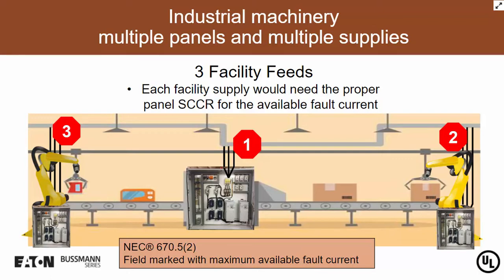And then we would need to determine how these panels are fed in terms of the supplies coming into this particular piece of machine. We would use the same method that I just outlined, trying to determine what the short circuit current rating is for a particular supply. It's important to remember that for each supply, we would have to identify what the short circuit current rating is for that supply, and then that would have to be provided on the main nameplate. So you could have multiple short circuit current ratings on a nameplate for a piece of machinery.